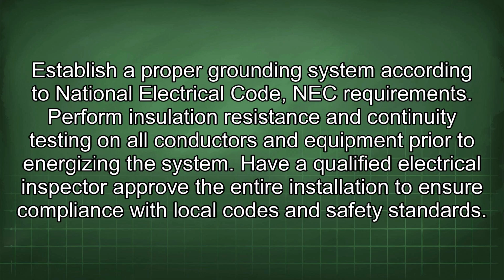Establish a proper grounding system according to National Electrical Code, NEC, requirements. Perform insulation resistance and continuity testing on all conductors and equipment prior to energizing the system. Have a qualified electrical inspector approve the entire installation to ensure compliance with local codes and safety standards.